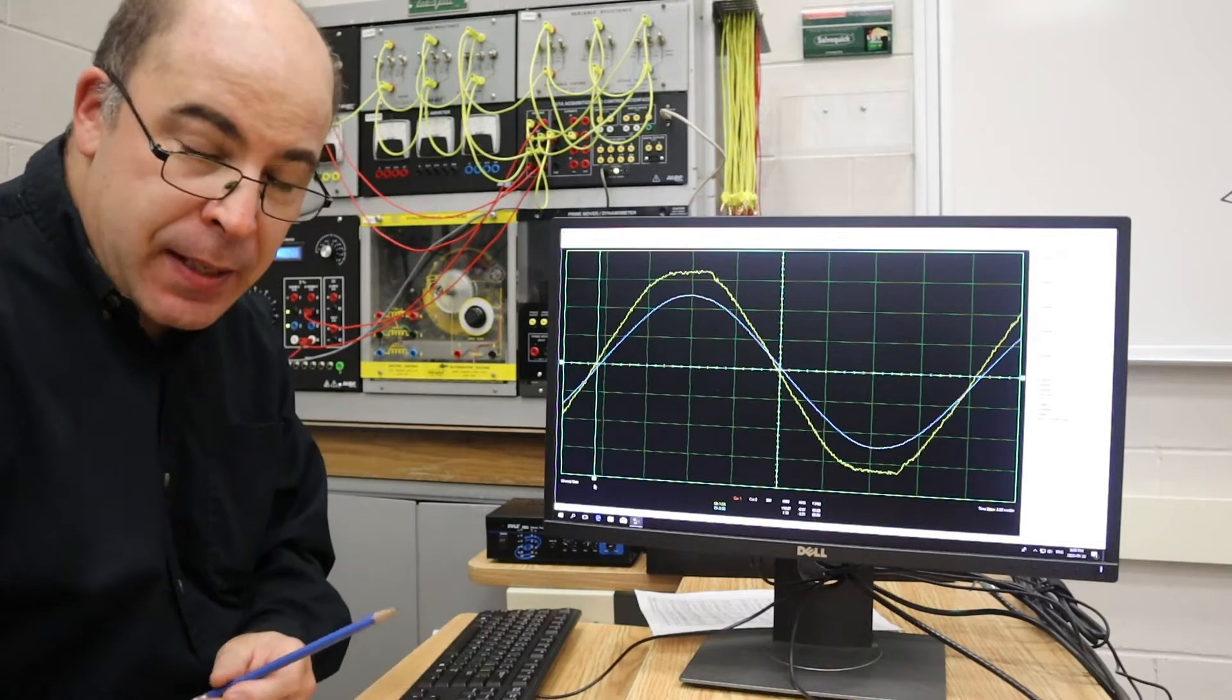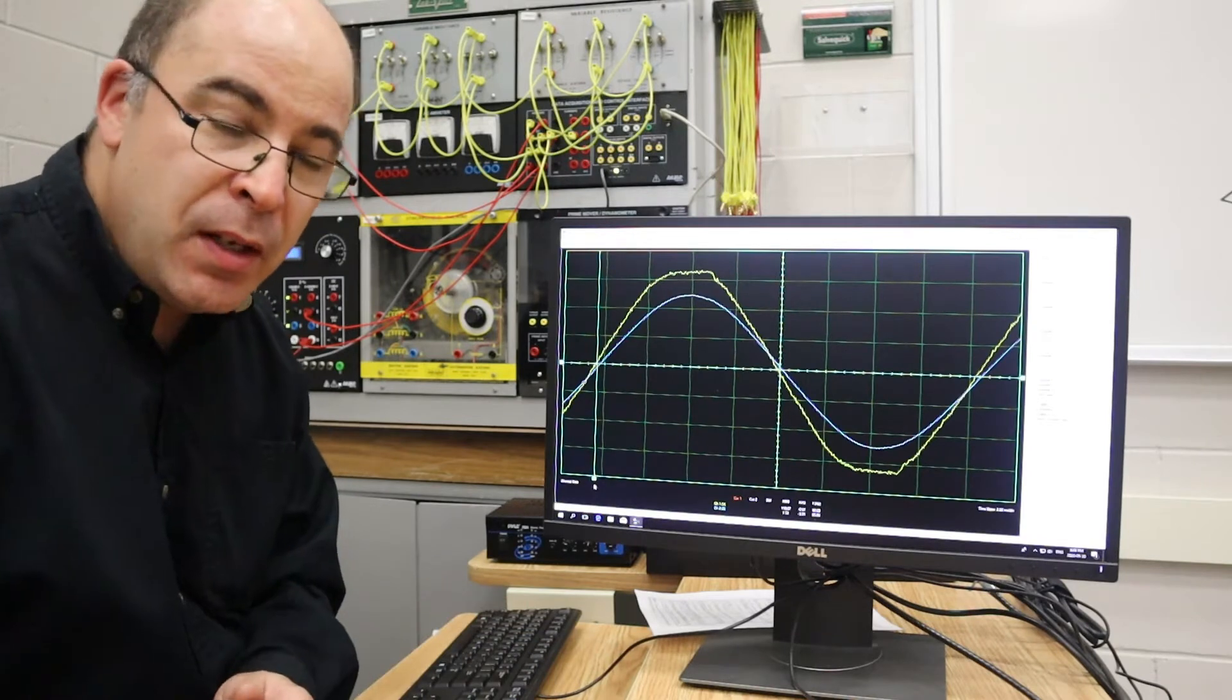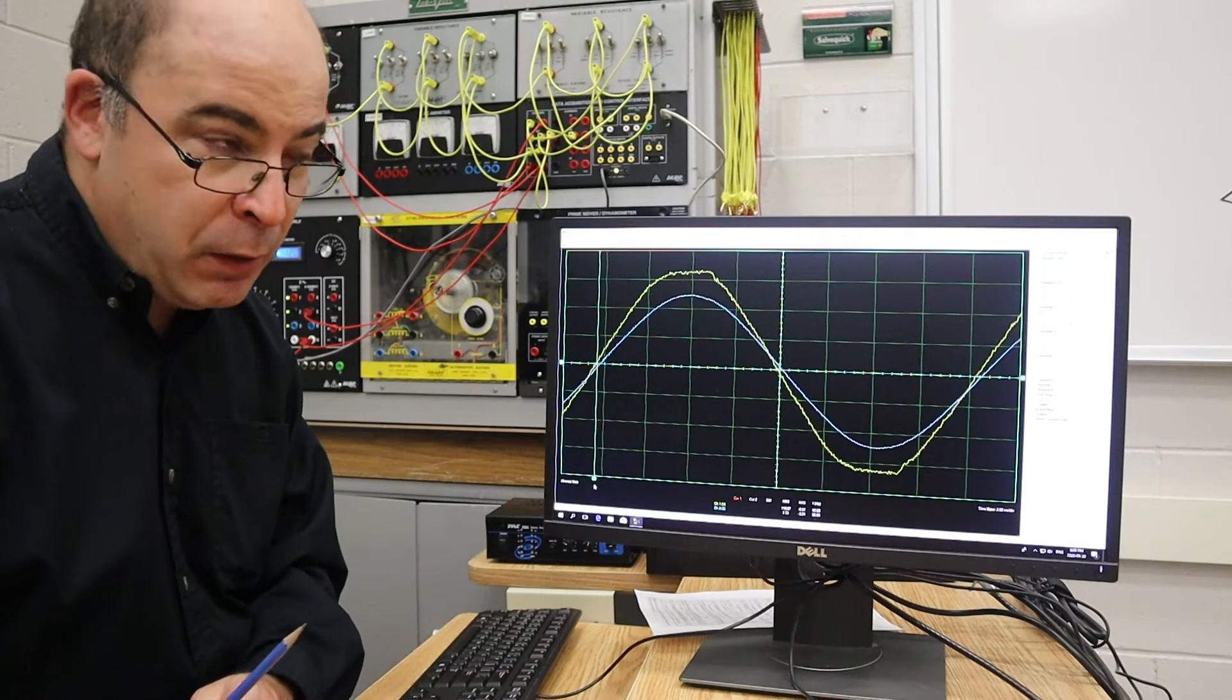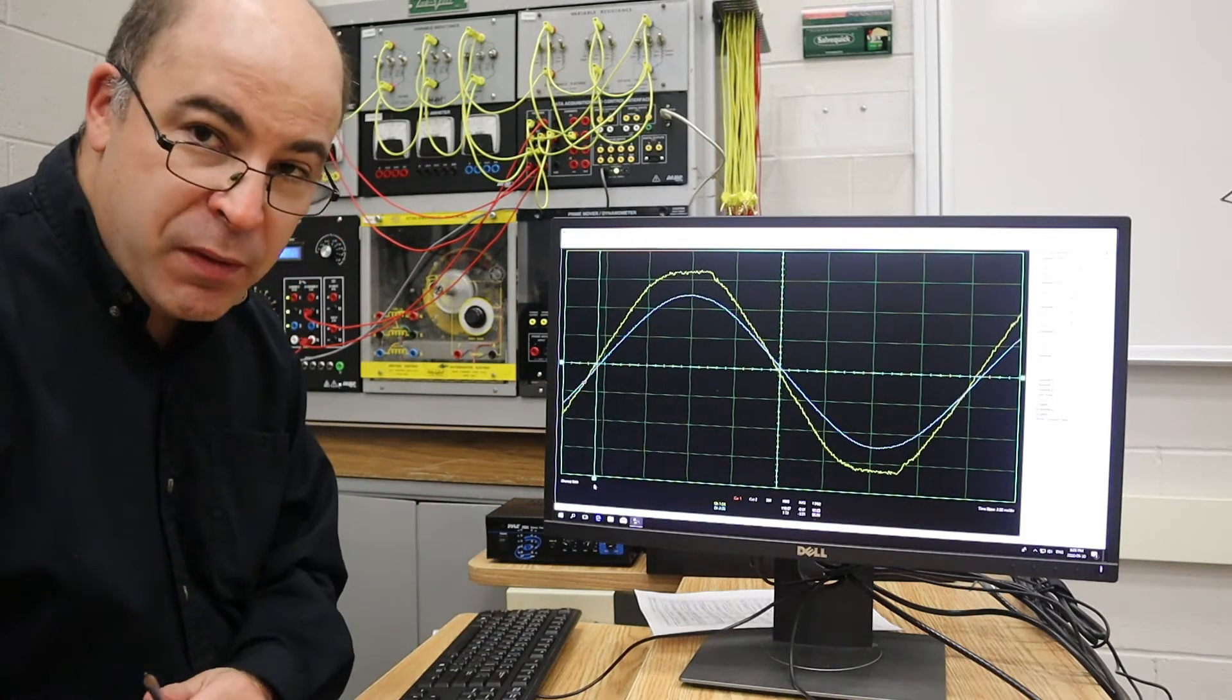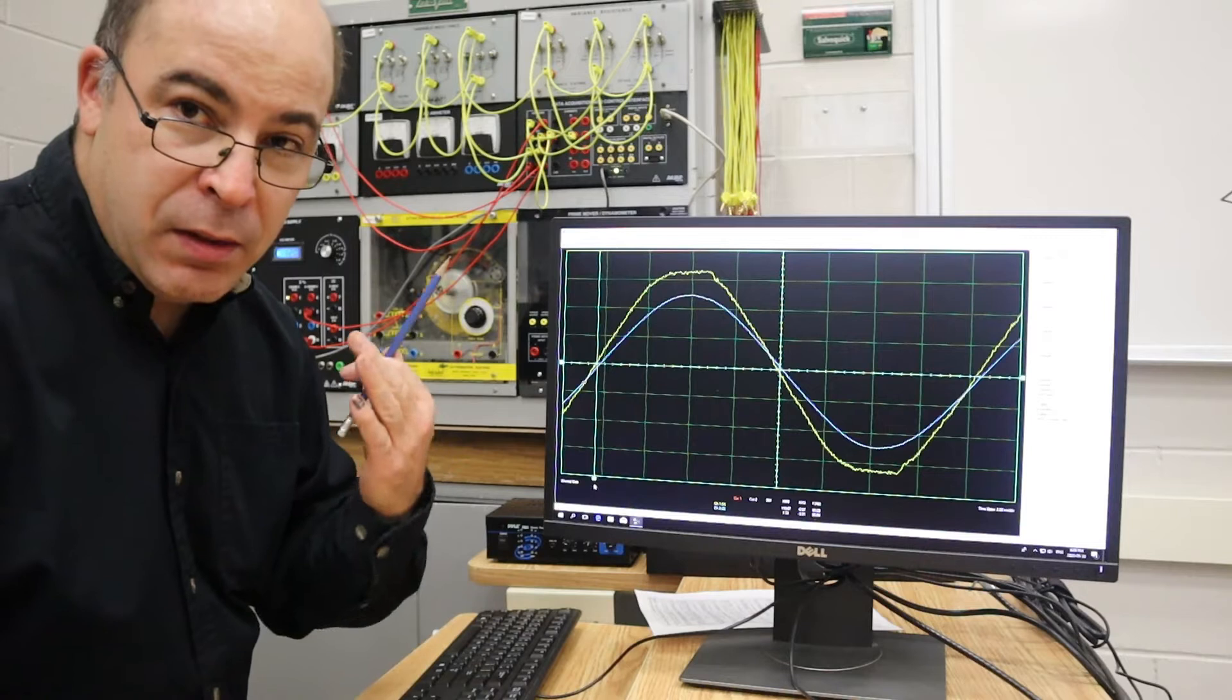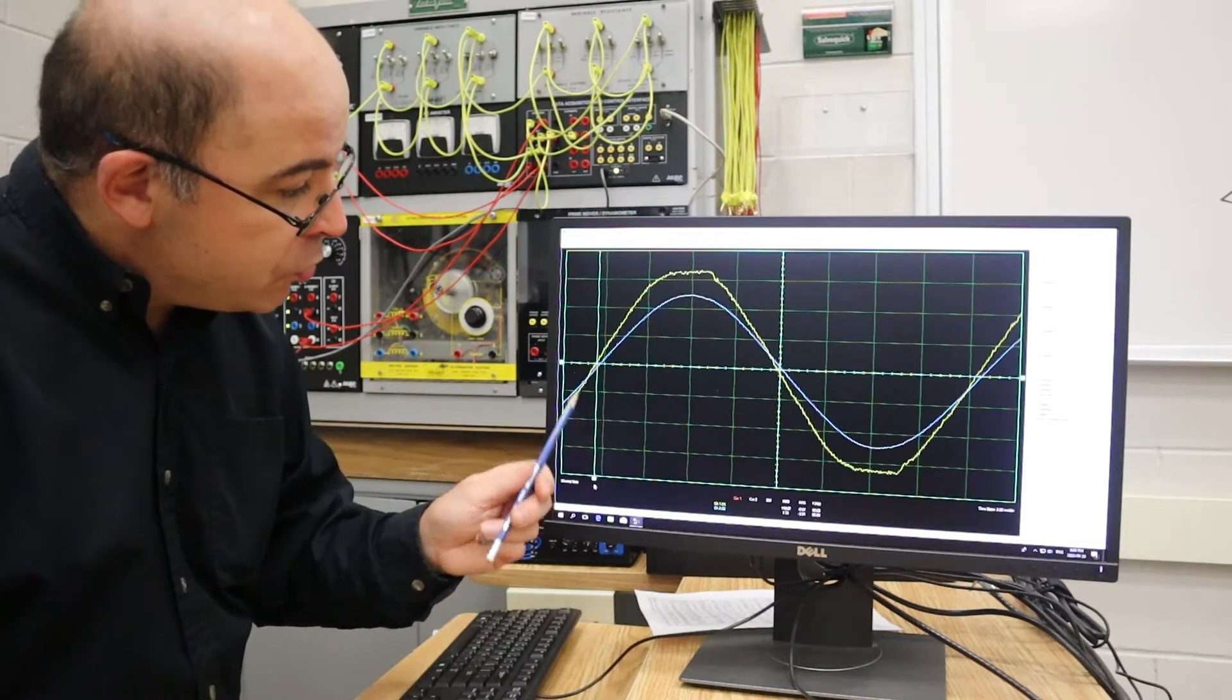What's happening is the load modules that I'm using, the resistive, inductive, and capacitive load modules, they're fixed values and they are fairly accurate, but they're not extremely precise. So we're off by about almost five degrees, but we are in the neighborhood. The trend is what we're looking at, specifically the voltage-current relationship.